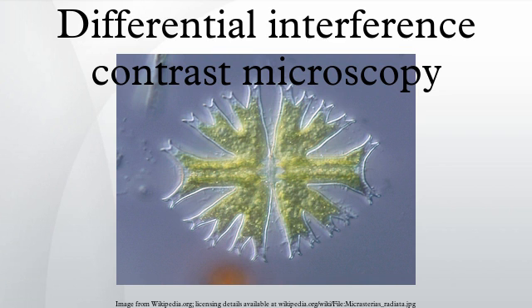The light path: Step 1 — Unpolarized light enters the microscope and is polarized at 45 degrees. Polarized light is required for the technique to work. Step 2 — The polarized light enters the first Nomarski-modified Wollaston prism and is separated into two rays polarized at 90 degrees to each other, the sampling and reference rays.